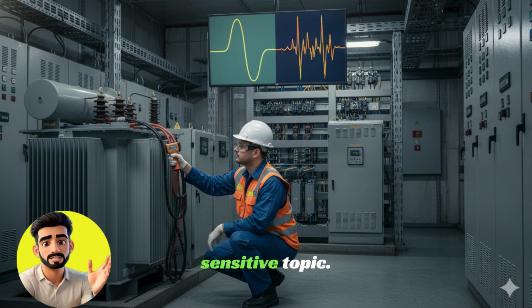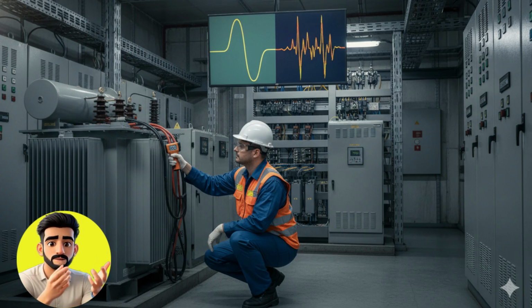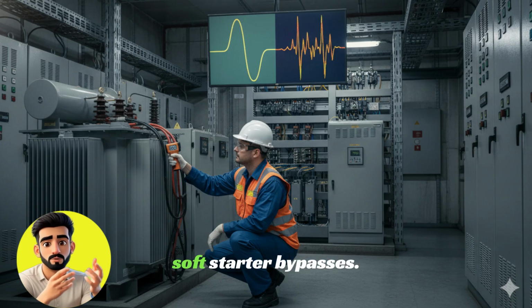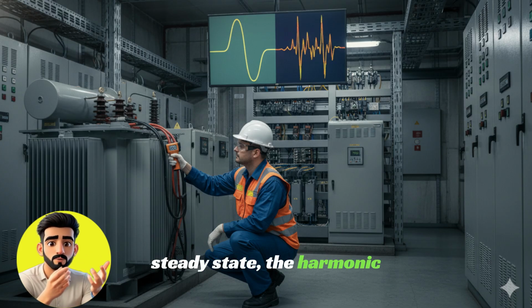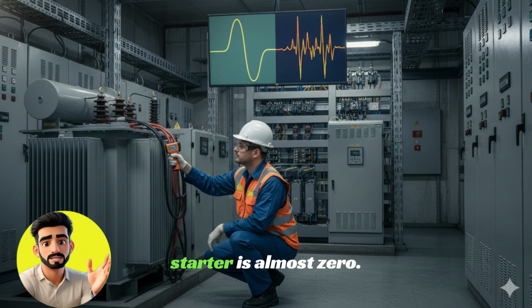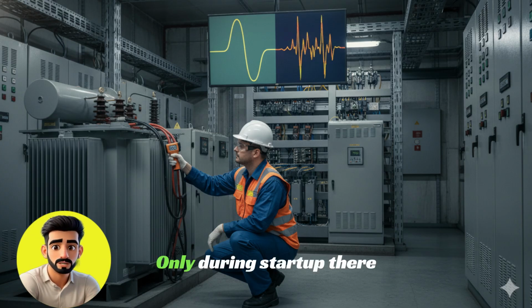Now let's understand a sensitive topic: harmonics. In normal operation, a soft starter bypasses. This means that in steady state, the harmonic impact of the soft starter is almost zero. Only during startup there is some distortion, which lasts only a few seconds.